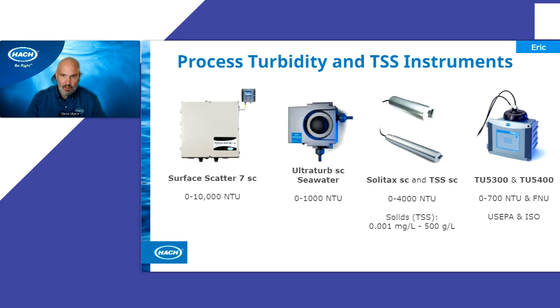That's probably the main range that we're looking at. I would also say, though, there will be a bit of a difference between the Solitax and the TSS-SC, with the TSS-SC working a bit better when we have higher concentrations of grease or FOG, so fats, oils, and grease.